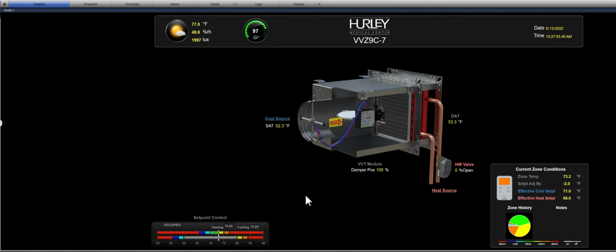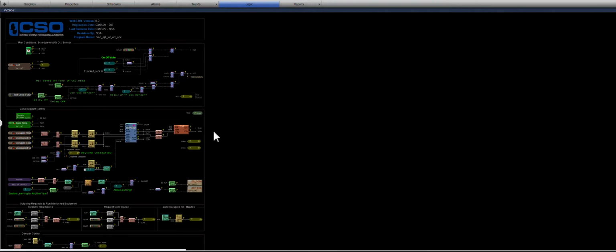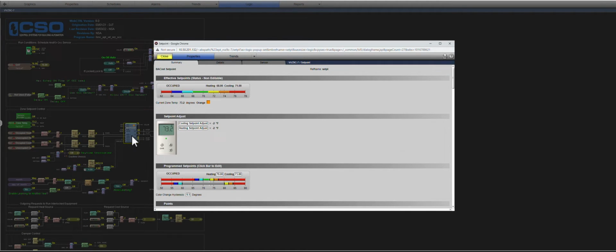All right, so let's find out why we're in the orange zone. We're going to go up to the logic and quickly look at the set point block here. We can see that's where our orange color is coming from for that thermostat image. If we click on it and take a look, we're going to see that they've adjusted their thermostat, and their comfort range, they're saying, is 71 degrees. So they're about 68 to 71. That seems like a narrower range than I think we agreed to put on the thermostat. I don't know if somebody's changed this or not, but we'll need to go back and look at that to verify it.